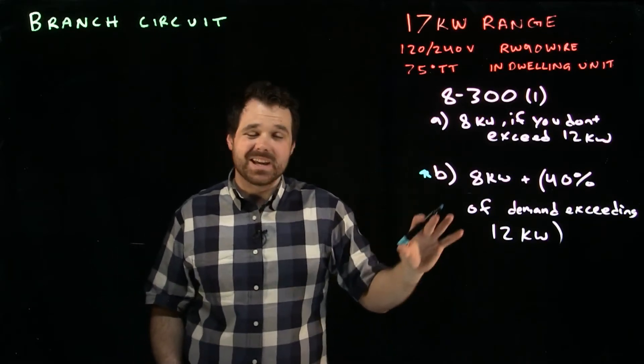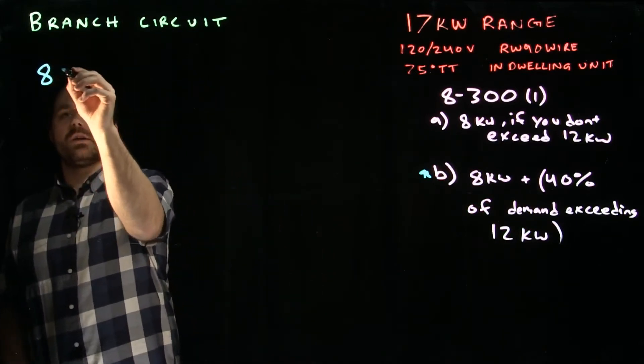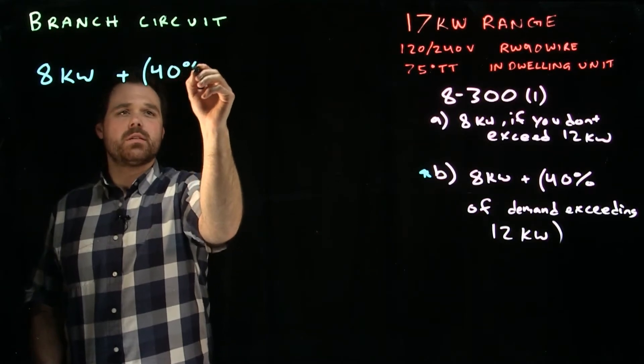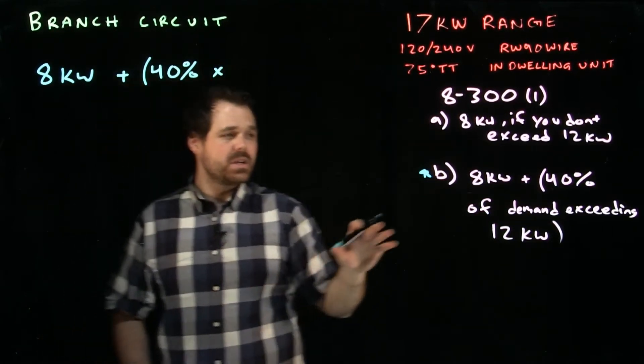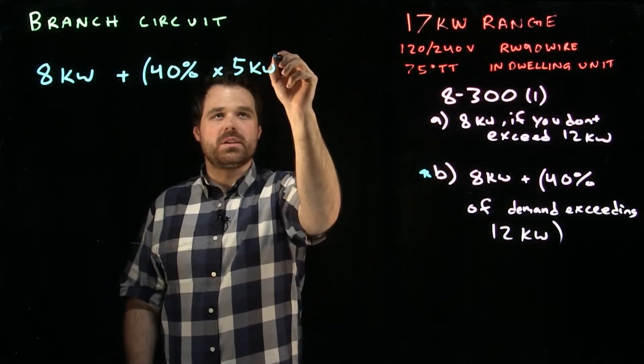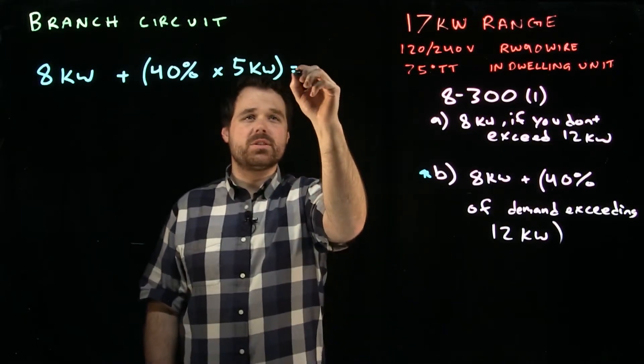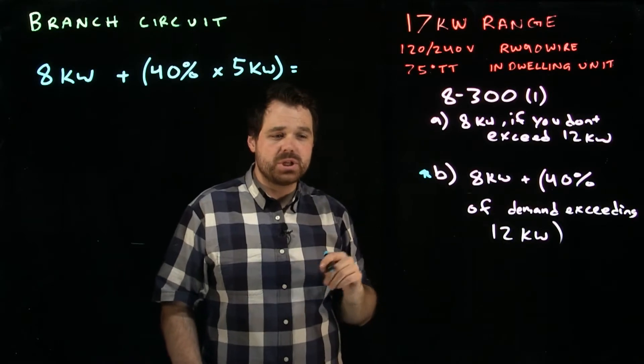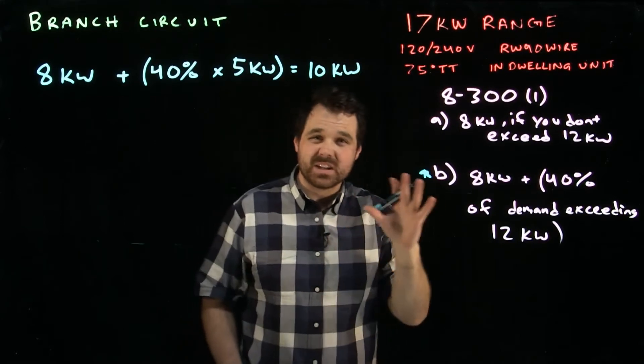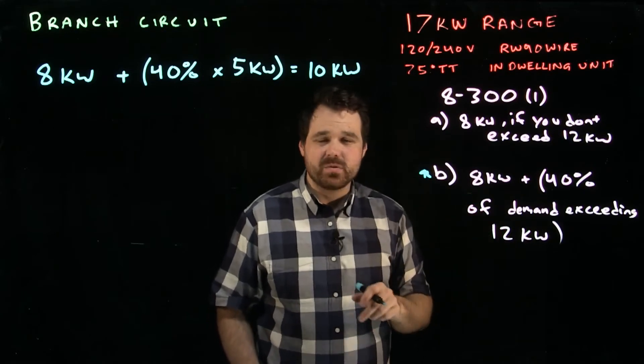So it tells us we're going to take 8 kilowatts plus 40% of everything exceeding 12. So we're going to go 8 kilowatts plus 40% times, in this case, we would have 5 kilowatts exceeding 12. Now this is going to give us our calculated demand of our range. In this case, we do the math and it works out to be 10 kilowatts. So 10 kilowatts is our calculated demand for this range. This is how much our wire is going to be able to have to provide to this range.